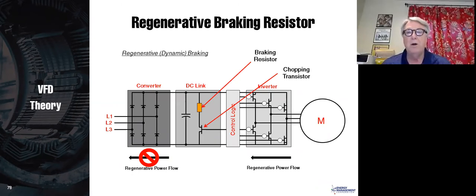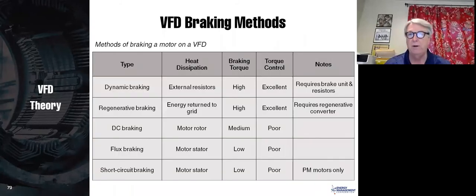Now, power can go from the input of the drive to the motor in a variable frequency drive. It cannot go from the motor back to the line unless you have a regenerative front end or a regenerative converter. So a lot of times we put braking resistors on here so that if a motor has to slow down too fast, or if it is on a downhill slope, the power can go through the inverter, but then it gets stuck on the DC link. That causes the voltage to go up and it will trip on overvoltage. So we can put in a braking resistor in there to basically just waste all that power and prevent you from tripping. And this talks about the various braking methods.